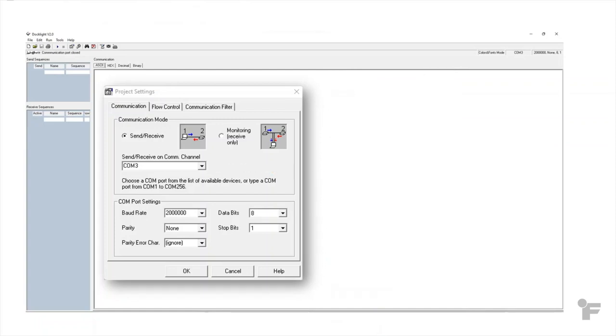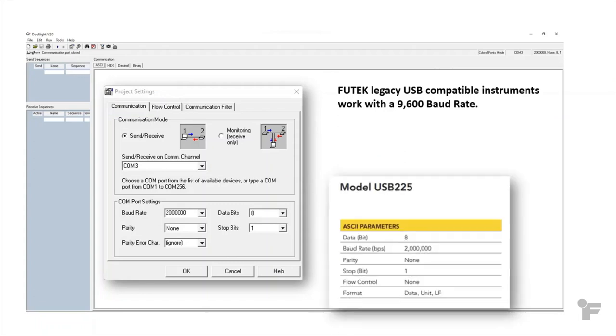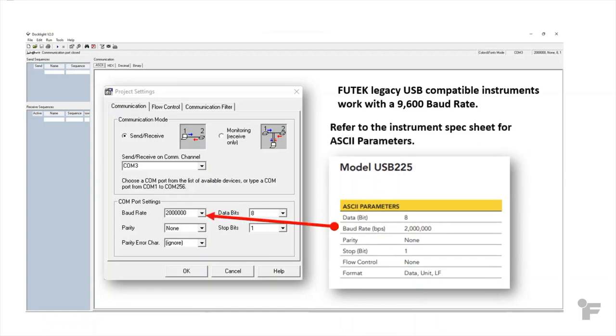The other thing that you'll want to know is what is the baud rate? FUTEK legacy USB compatible instruments are set at 9600 as their baud rate, but you'll want to refer to the instrument spec sheet for the correct baud rate to use.